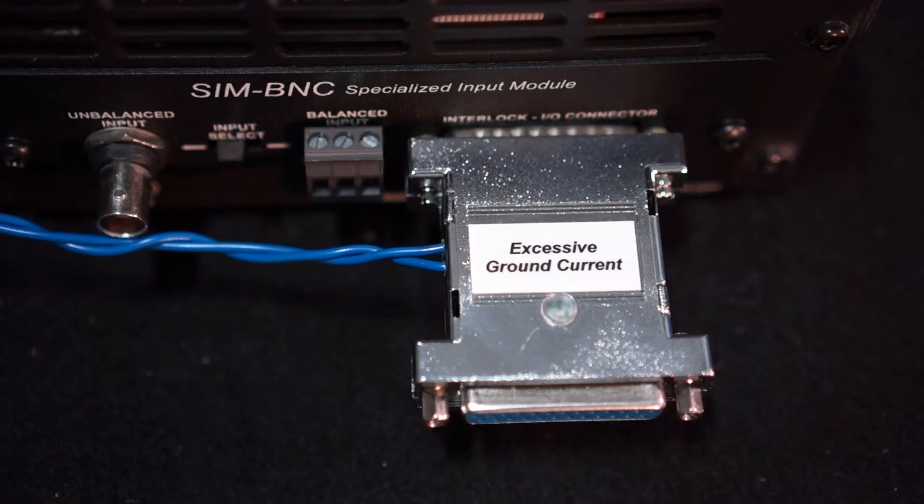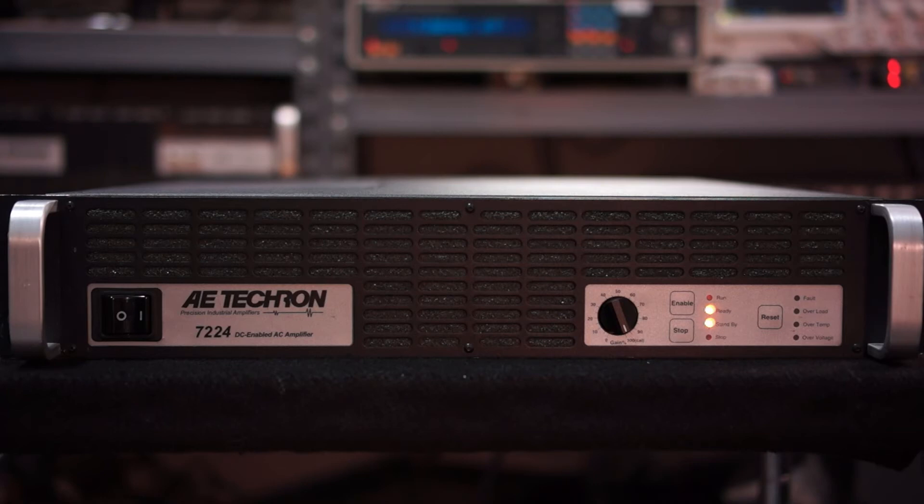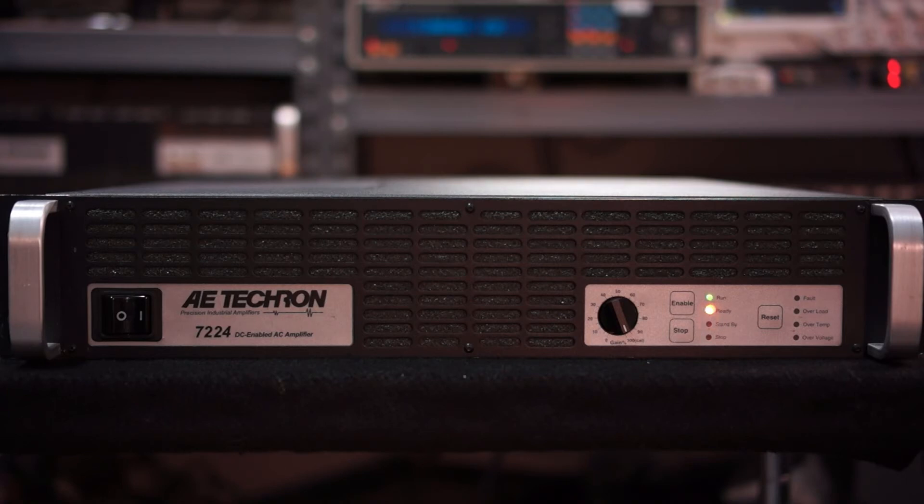When active, the GCL module will provide a visual indication that it is operational by lighting an LED on the enclosure. Once the ground differences return to an acceptable range, the circuit will release the amplifier from its forced standby condition and allow it to return to either a run or ready state depending on the amplifier feature selections.